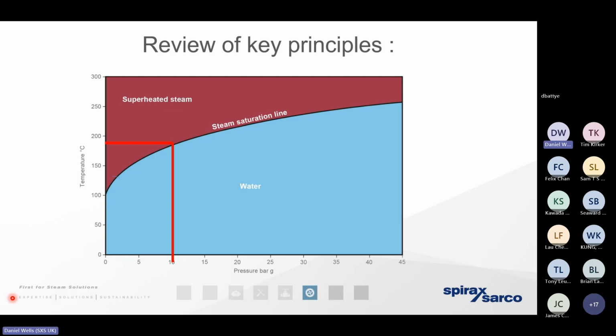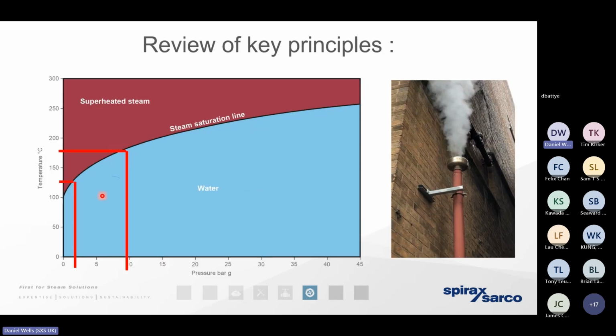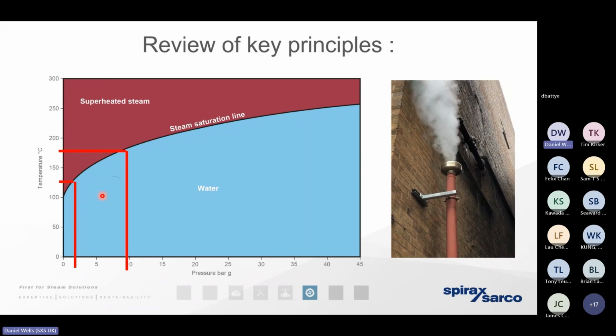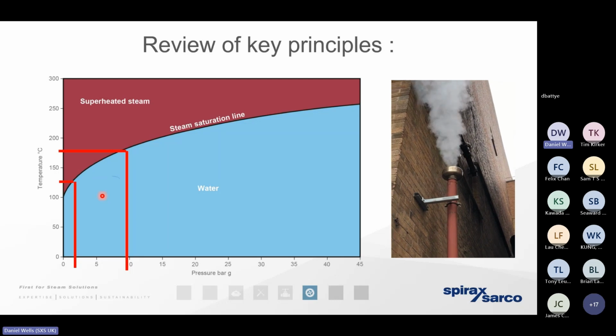Now at that pressure, condensate can exist as a single phase, non-compressible liquid quite happily. But if we depressurize the steam, and if the steam trap has failed in the open position, then both the steam and the condensate are going to need to depressurize at the same rate. So let's think about a steam trap that's failed open at 10 bar gauge. If the steam and the condensate are depressurizing from 10 bar gauge, 184 degrees, to 0 bar gauge, we can see that the steam, and especially the condensate, can only exist at 100 degrees. It means that the condensate has got to cool down by 84 degrees. It's got to give up a lot of energy. And the only way the condensate can do that is by changing state from a single phase, non-compressible fluid and expanding by a factor of more than 1600 times.